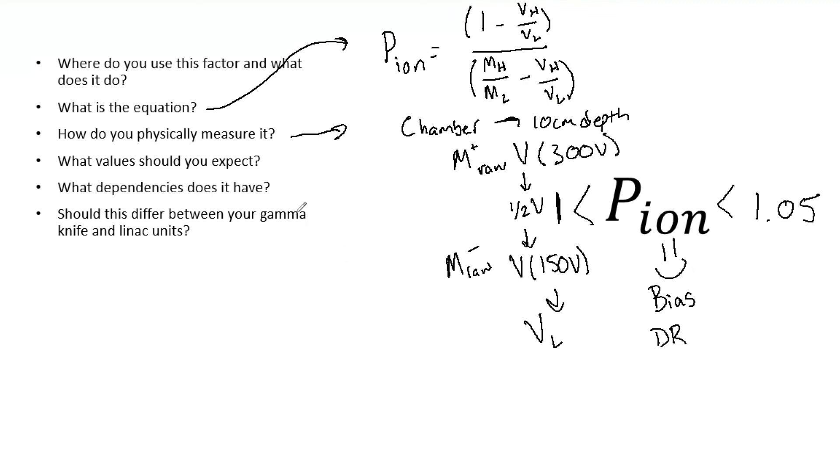Because of that, should the values between gamma knife and LINAC differ? And they should. So continuous radiation first of all is going to have the lowest P ion values.